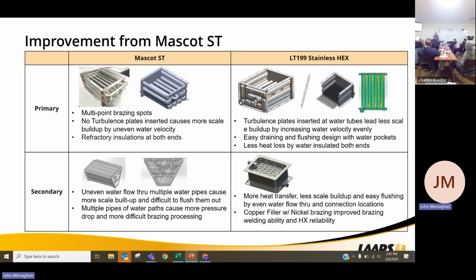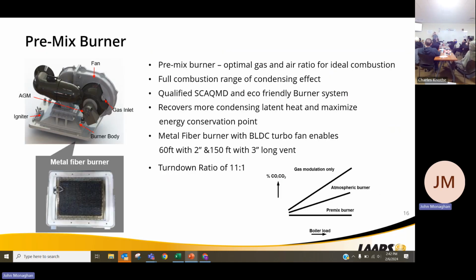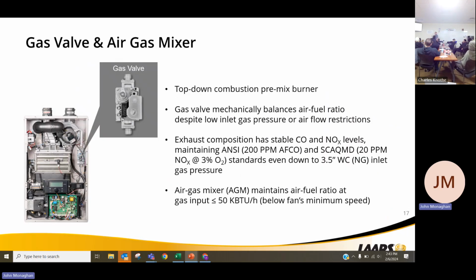We've basically listened to what the market was telling us, what we could improve on, and added all those features into this product. The burner is going to be a premix burner. It's going to have a fiber mesh burner. There's also, as with our heat onlys on our boilers, an air screen to protect from any debris going into it. And it is an 11-to-1 turn down ratio. We can go 60 feet with 2-inch, 150 feet with 3-inch for venting.